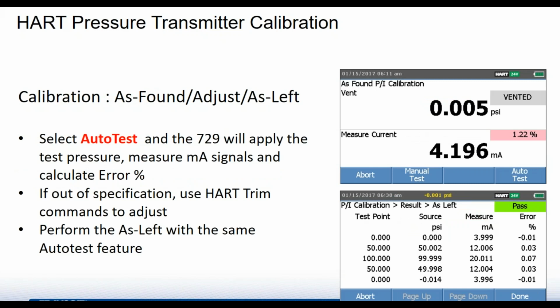And we go through the same process as we did with the hand pump calibration. The key difference is when you go to do that as found test, remember when we talked about using a hand pump, you have to go to each pressure point and stop, settle it, get that reading, and then press accept to get that pressure point. Well, with the automatic pressure calibrator, you basically just press start. Just do auto test, and the calibrator, in this case the 729, will apply pressure to each test point. In this case, it was a 3 up down test.